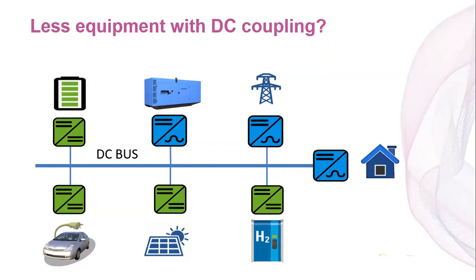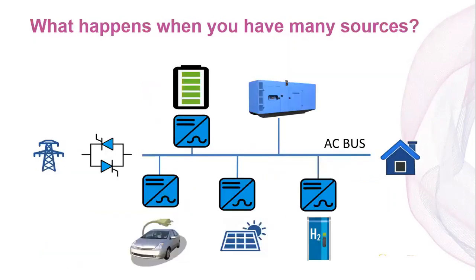One of the problems with AC microgrids is that when there is a grid disturbance, you have to quickly disconnect the grid from the microgrid. For those cases, they use static transfer switches, fast switches that disconnect within a fraction of a cycle. But then the problem is that this device produces losses and is used very little in the microgrid.